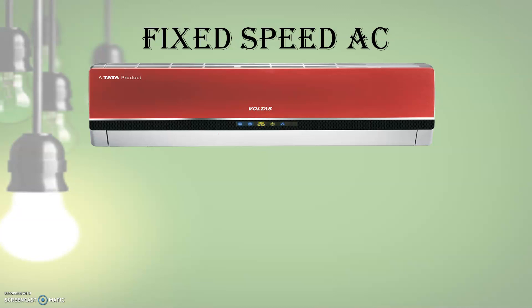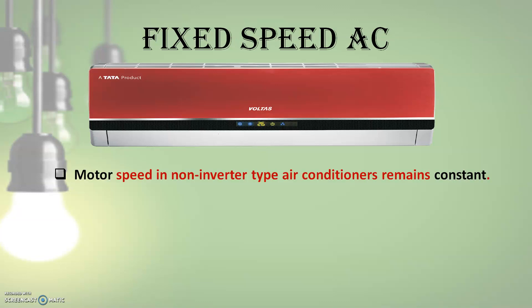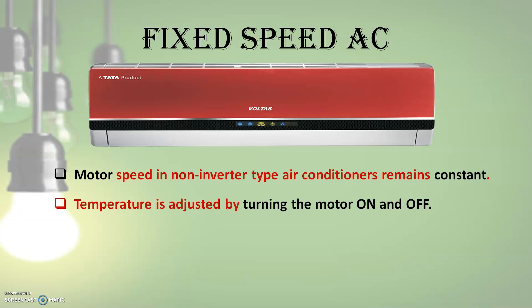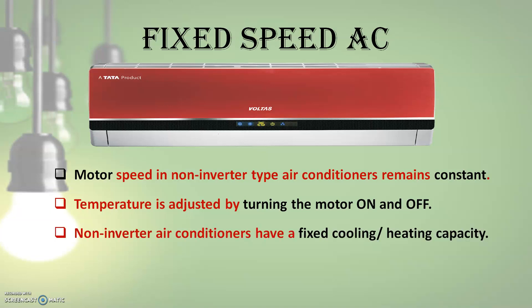In a fixed speed or non-inverter type air conditioner, the motor speed remains constant and temperature is adjusted by turning the compressor on and off, which consumes more energy. In other words, non-inverter type air conditioners have fixed cooling or heating capacity and can only control the indoor temperature by starting and stopping their compressor motor.